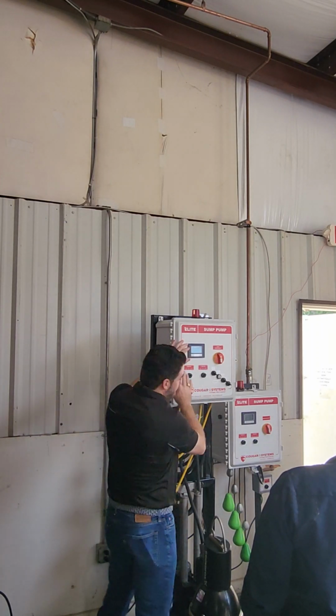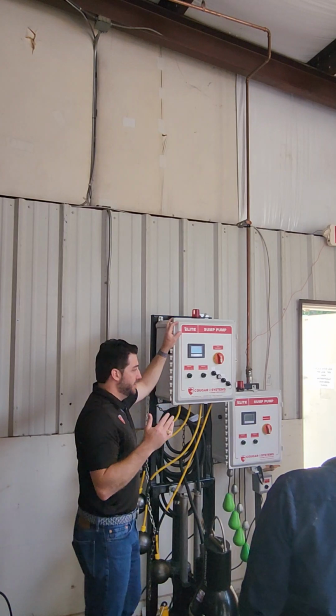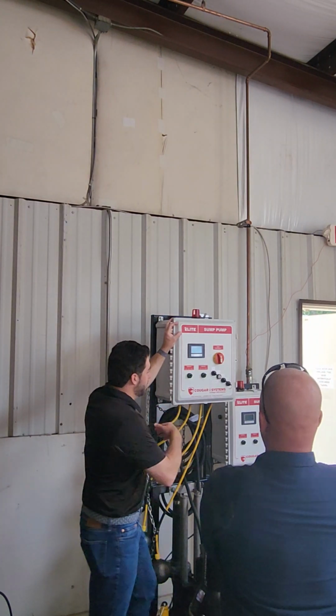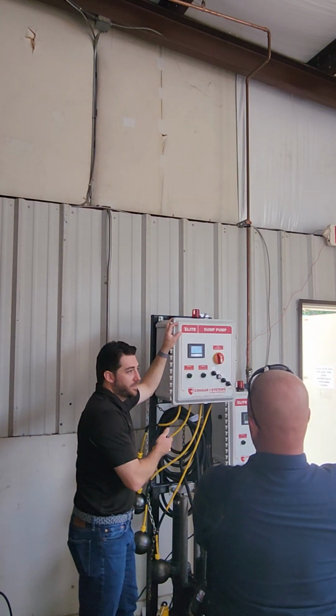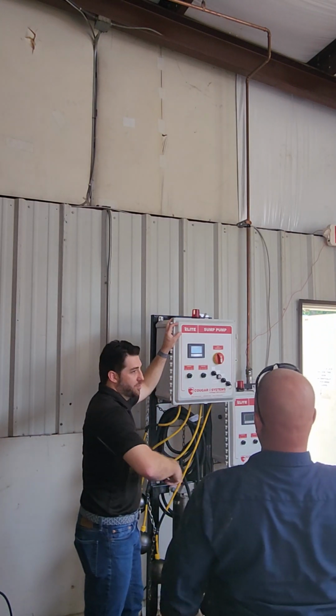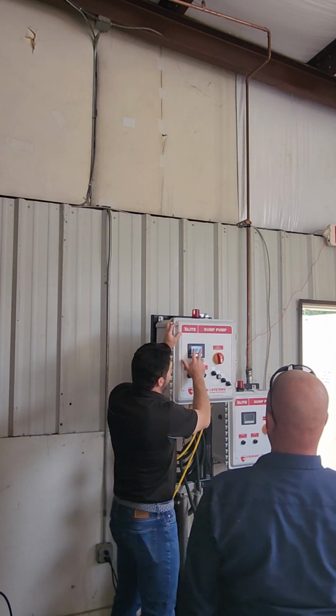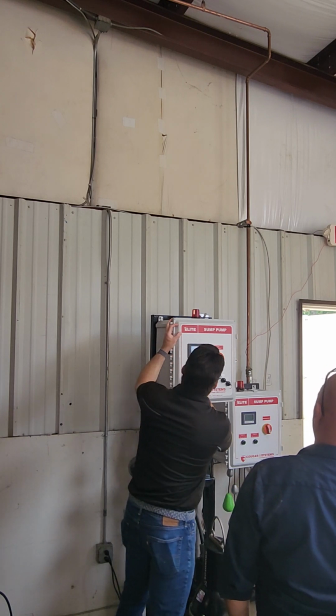So if you see those 2 run times and they're way off, that probably means that one pump is set to be the lead and not the other, right? So that one pump is just running all the time. You want to have even run time on the 2 pumps.